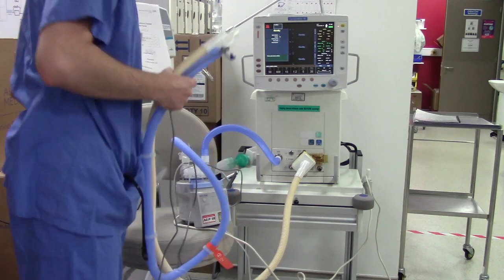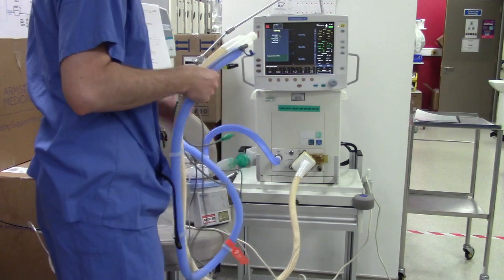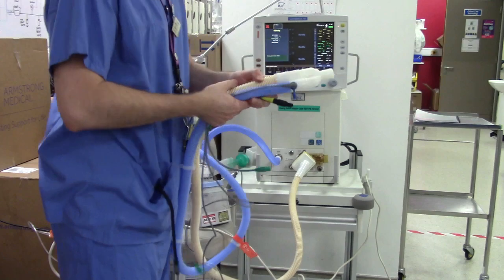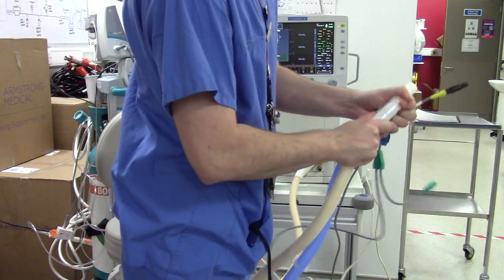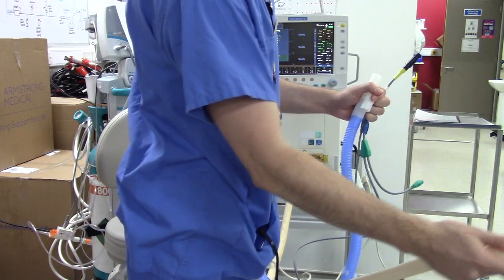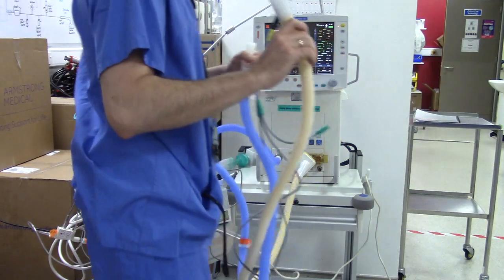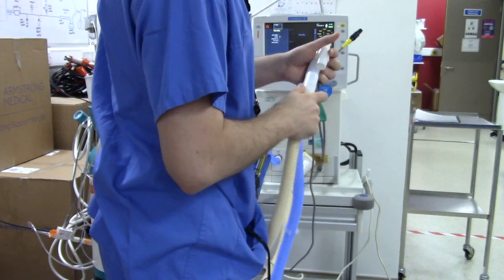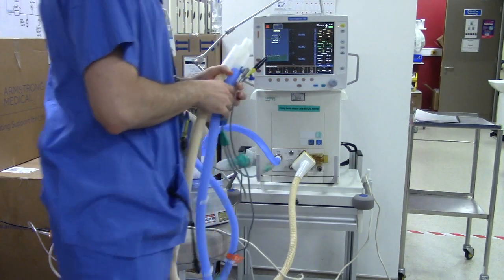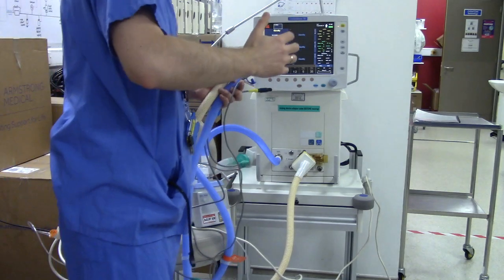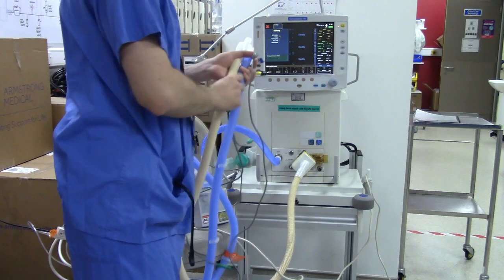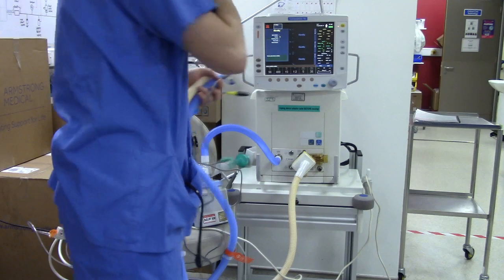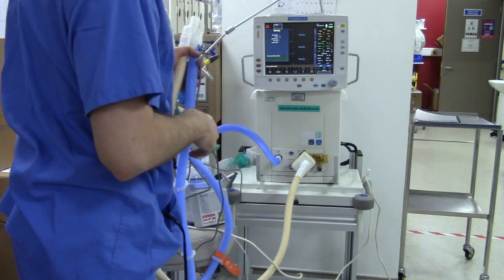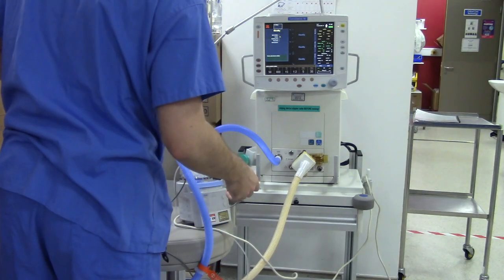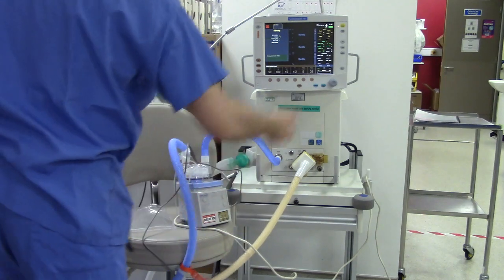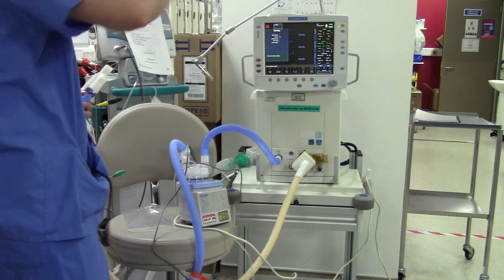Then we have the other set of cables, which is called the heating wire. The function of this cable is to heat the wires that are inside these circuits. So these circuits, you see the wire inside? Yep. Yeah? So these circuits are heated. This way you will have less chance of producing condensation. Yeah? Because when you are running warm air through a cold circuit, it will condense. When it condenses, it will form fluid in the circuit, and it will kind of form an occlusion for the air going to the patient. Yeah.